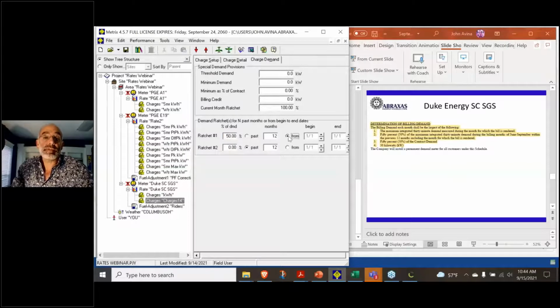It's a little bit of a different ratchet than what we saw. So June, I think 6, and September, I believe, is 9. So 50% of the maximum demand during the billing months of June, September. Yes, and 50% of contract demand. So we'll put in this 50% of contract demand. I'll show you where to put in contract demand in a minute, or 30 kilowatts. Minimum demand is 30 kilowatts.